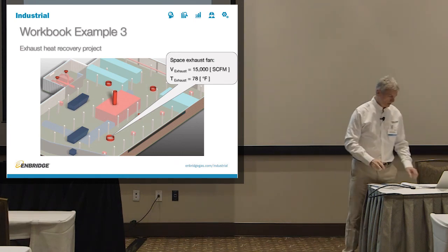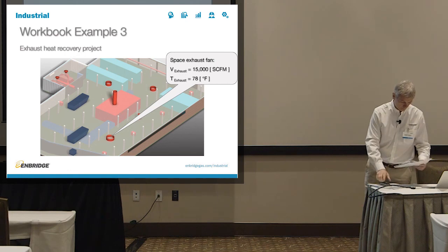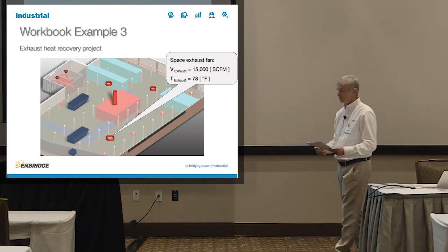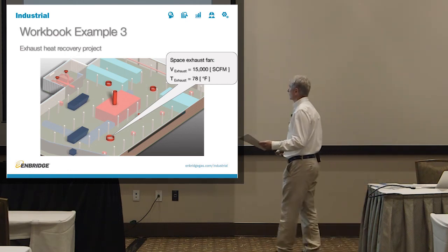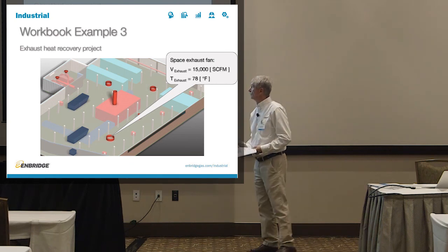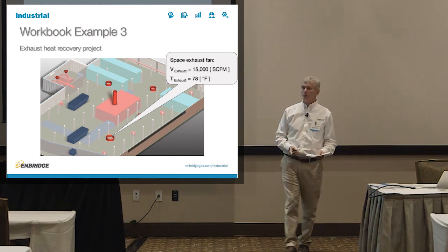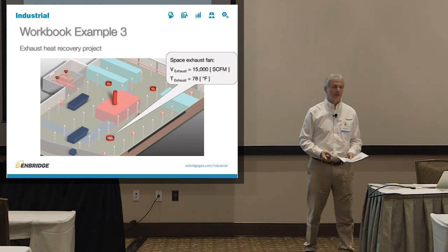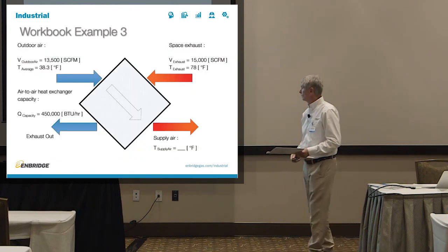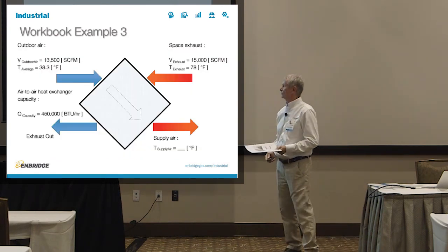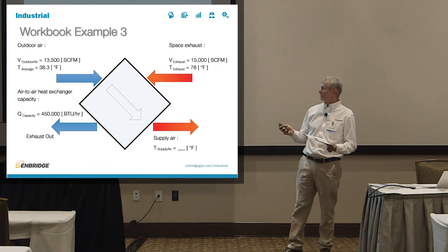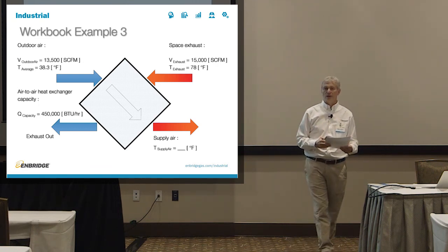Okay, so let's do the last workbook example, in which we will do heat recovery out of the space exhaust fan, 15,000 CFM of air, leaving the facility at 78 degrees F. We'll put it into an air-to-air heat exchanger that can recover 450,000 BTUs per hour max.